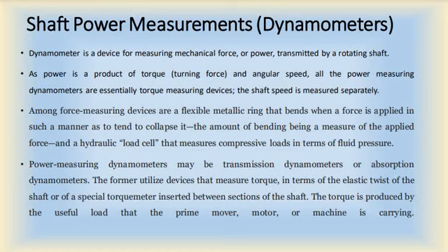When the DC machine is employed as a generator, the generated power is dissipated in a resistance grid, or we can recover it for further use. The DC dynamometer can also be adjusted to provide any torque from 0 to the maximum design value for speeds from 0 to some base speed value of the machine.